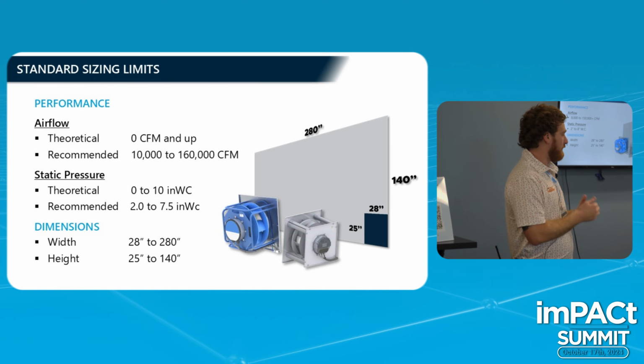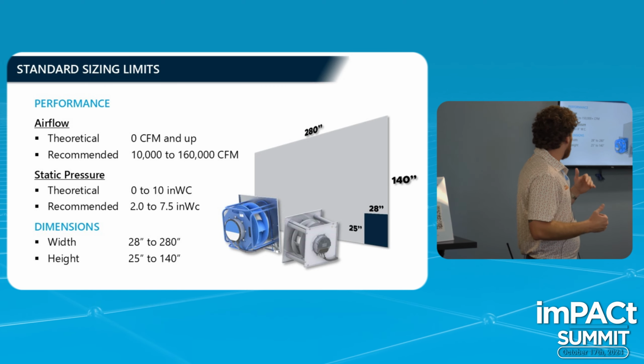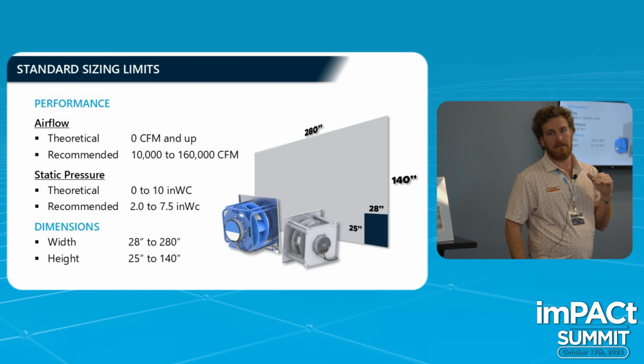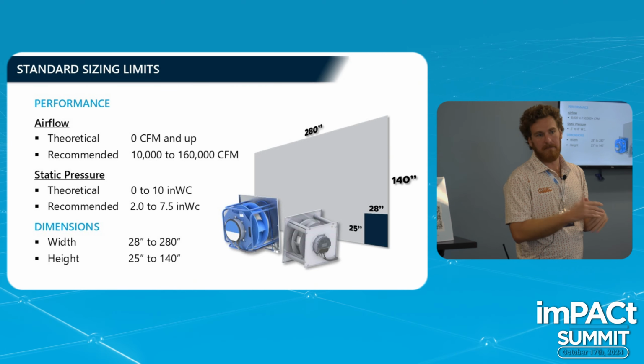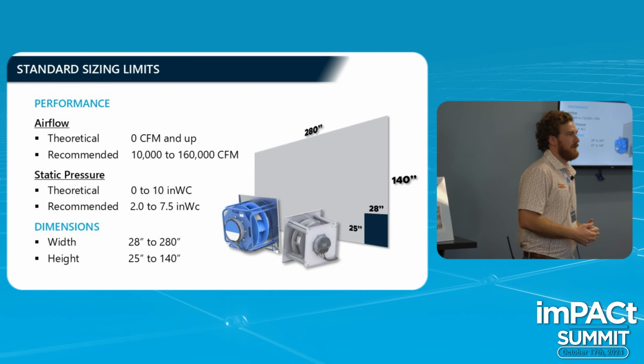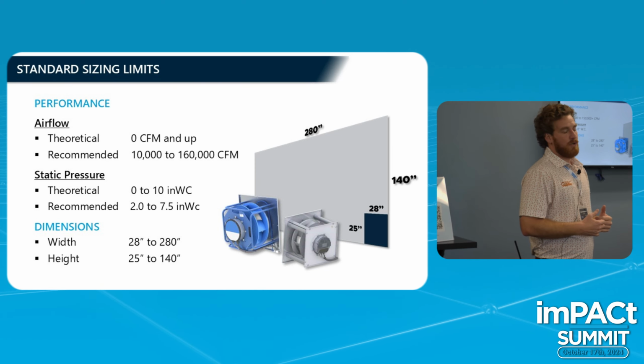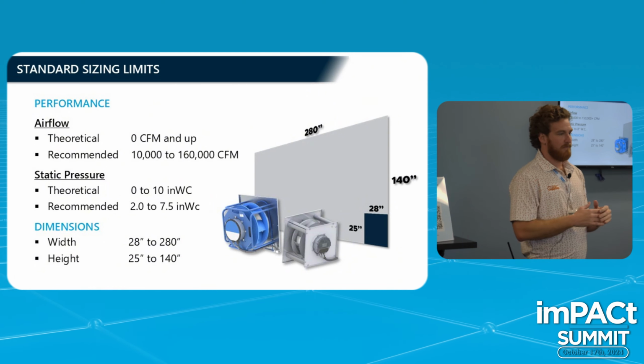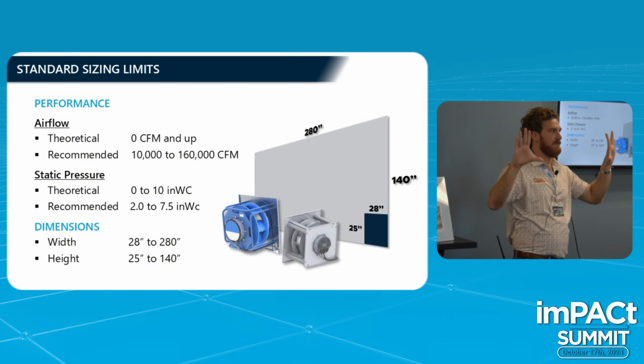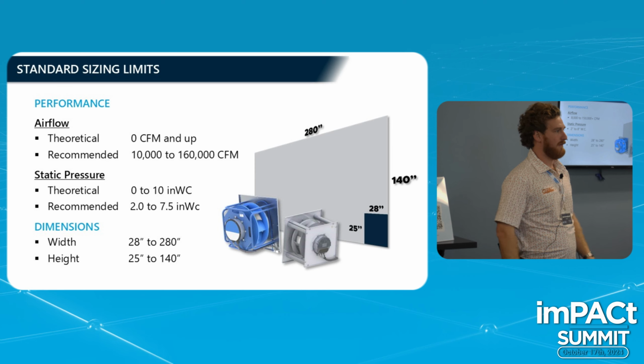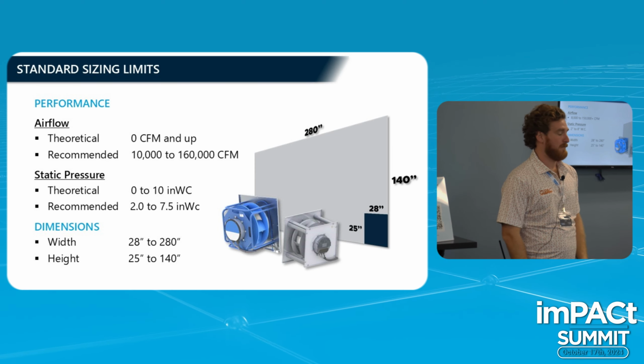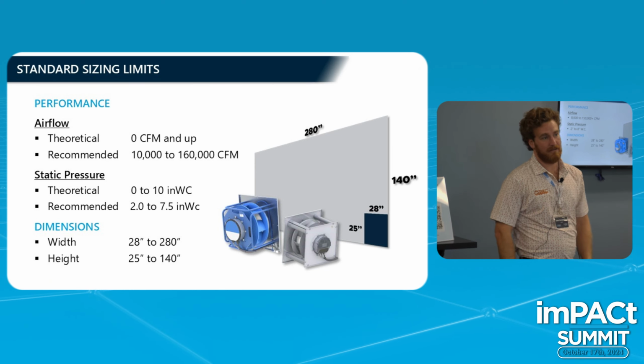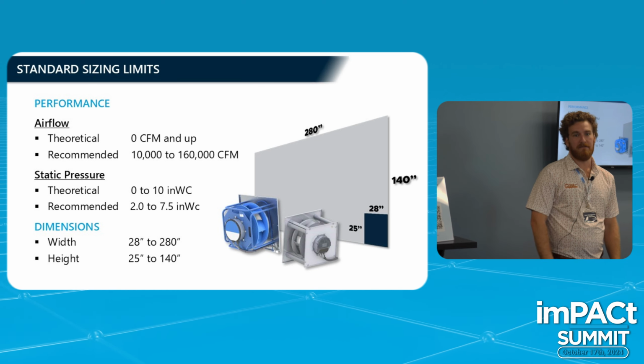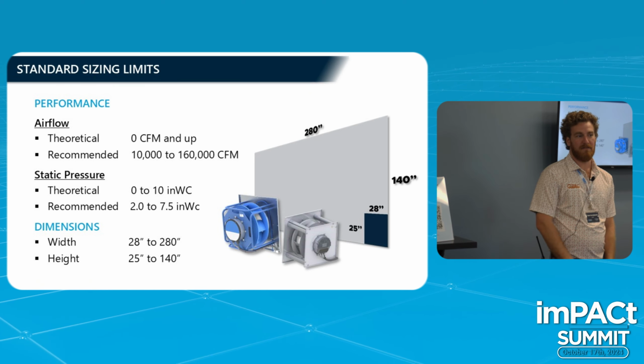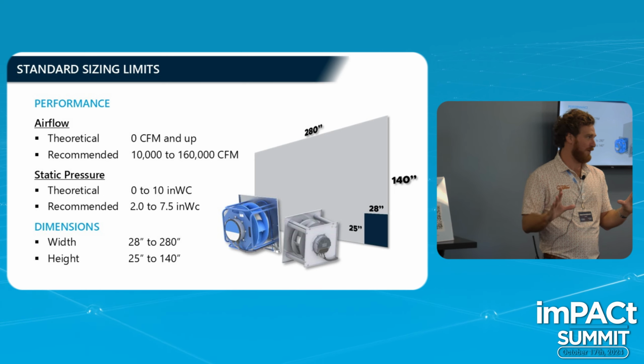But in general, the efficiency is there when you're between 2 and 8 inches of static pressure and 8,000 CFM, or 5,000 CFM and up. We have some massive systems out there, like 250,000 CFM. You'll have maybe 60 ECMs on a plenum wall inside of a mechanical room. Some of the projects that the Weikerts were talking about are massive. So the sky's the limit. If you can fit the fans in there and it meets the performance requirements, then you're good to go.